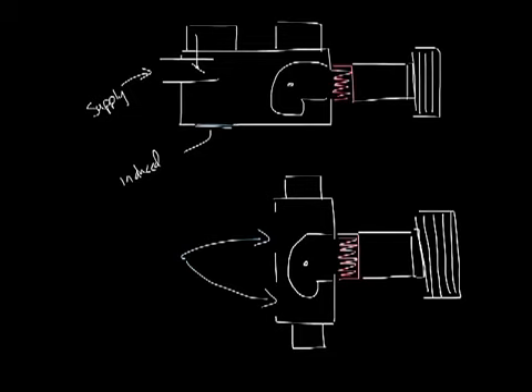Now ideally, you'd want to get rid of the fan boxes altogether, but the challenge is, how do you handle the higher loads of the perimeter? Another challenge that I haven't mentioned is that both the overhead fan box system and the underfloor fan boxes ducted to the linear bar grills break through the stratification layer that I discussed in the last podcast. So let's draw a side view of these systems. The overhead fan box will have a throw that looks something like this.